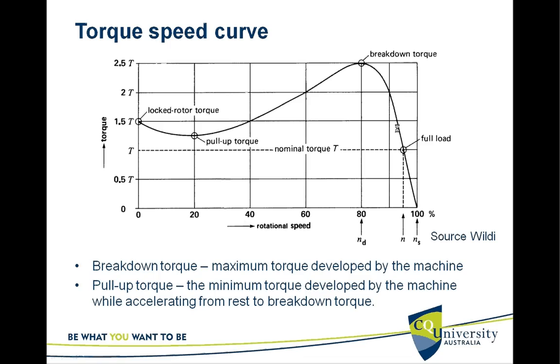The motor settles down at full load, which is the usual normal operating point. The breakdown torque is the maximum torque developed by the machine. The pull-up torque is the minimum torque developed while accelerating from rest to breakdown torque.